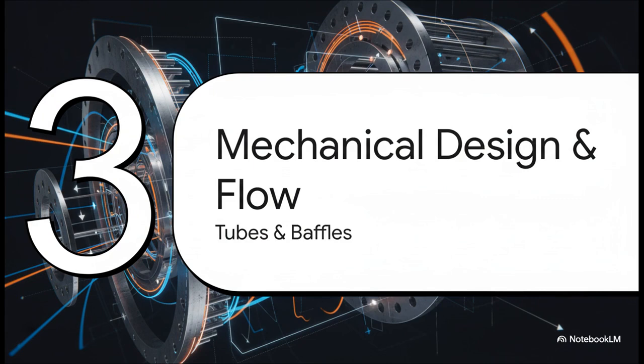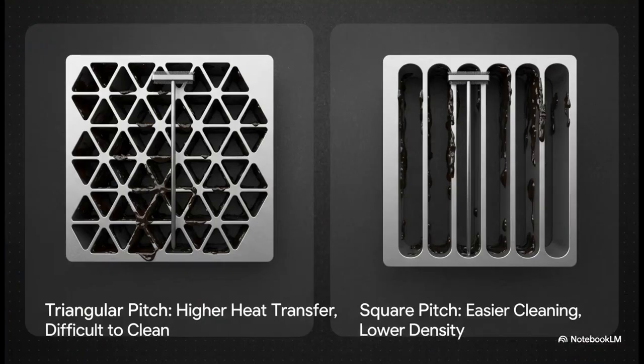All right, let's move inside the exchanger and look at how the physical layout of the tubes and baffles is actually engineered to squeeze out maximum performance and reliability. So one of the first mechanical decisions you're going to make is how to arrange those tubes. A triangular pitch lets you pack in the absolute maximum number of tubes, which is great for boosting heat transfer. But it creates these really narrow lanes that are a nightmare to clean. On the other hand, you have a square pitch. It's less dense, sure, but it gives you these nice clear lanes for mechanical cleaning.